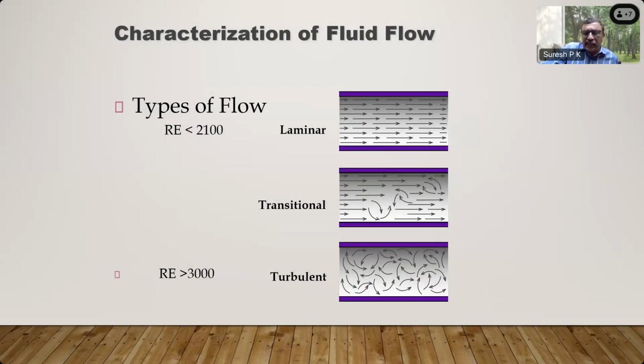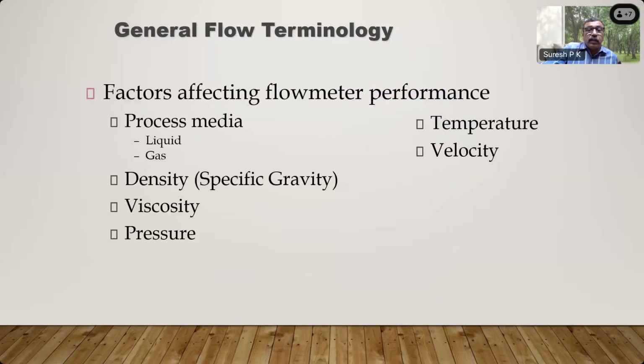These are all basic physics which you have probably already studied at school level. Then, flow meter performance is also affected by density, by viscosity, and can get affected by pressure, temperature and velocity. Take the case of viscosity. In a positive displacement flow meter, when the viscosity is very low, the probability of error is more. When the viscosity is higher, the probability of error is less.